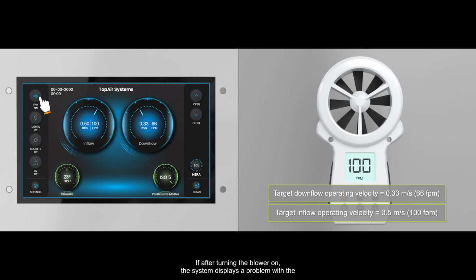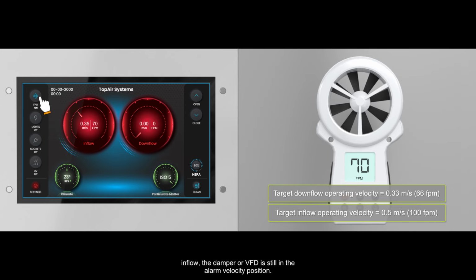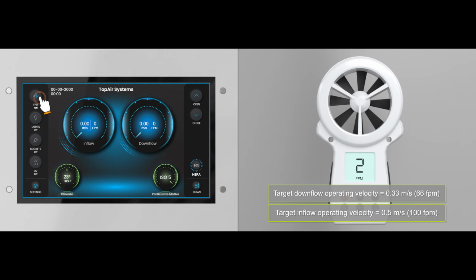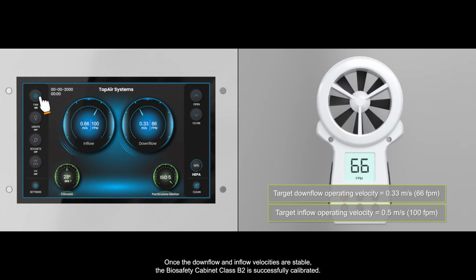If, after turning the blower on, the system displays a problem with the inflow, the damper or VFD is still in the alarm velocity position. In this case, return it to the operating velocity position and repeat the verification calibration process. Once the downflow and inflow velocities are stable, the BioSafety Cabinet Class B2 is successfully calibrated.